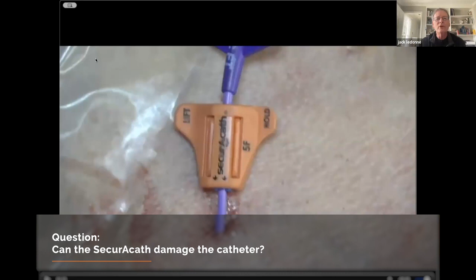And there was a question about damaging the catheter. Yep, you go ahead. It won't damage the catheter. No, you will not, because of the way the anchor feet are, it's not sharp enough. It's never at an angle, but it's definitely not sharp enough to slice a catheter of any material. And we do insert silicone catheters also, and it has never done any damage to a polyurethane or silicone catheter. Yeah, and we had to test and approve that before we could ever get the device approved too. So it is blunt, non-sharp, and they do not cause any sort of damage to the catheter or really any of the tissue in the sub-Q. It's a blunt dissector, so it's just going to push things out of the way. It's not going to cut through anything.